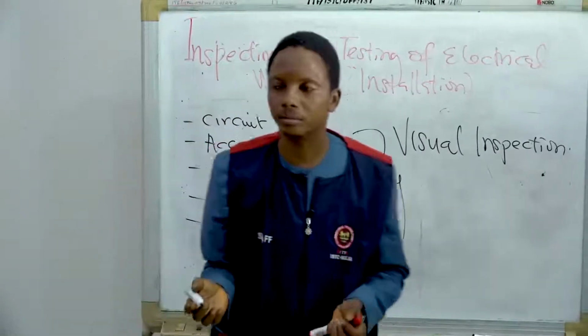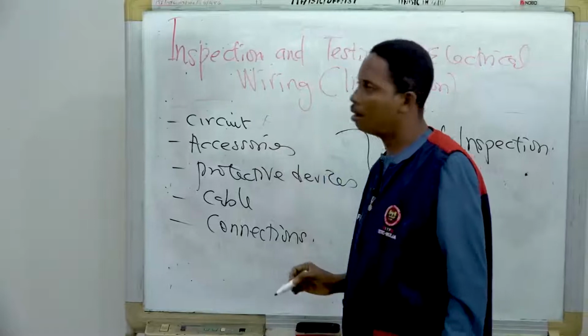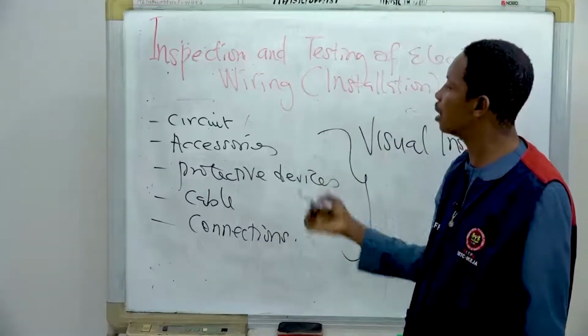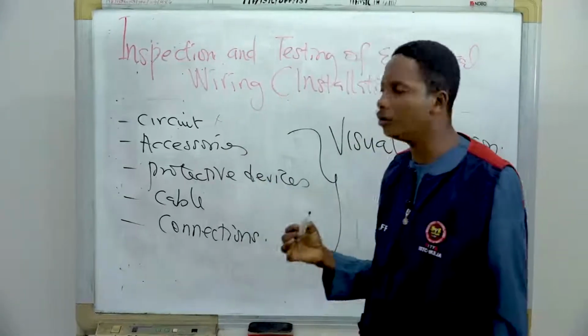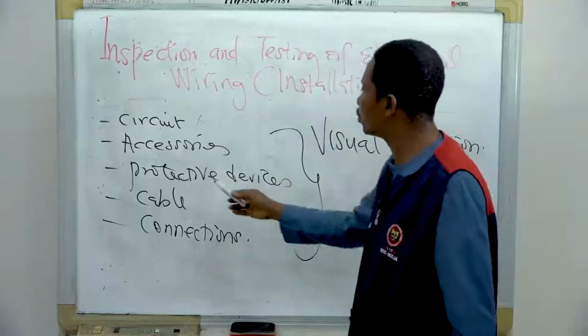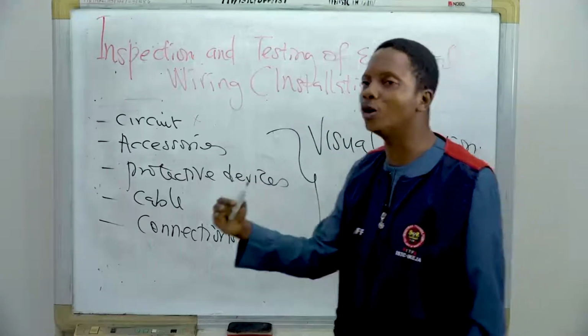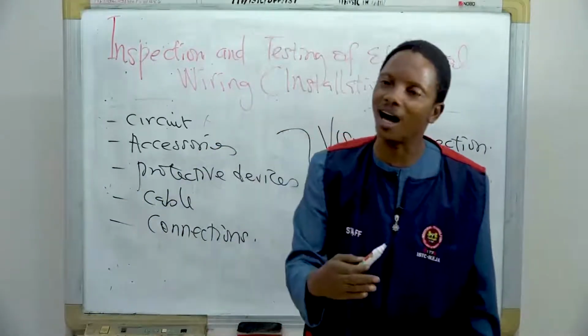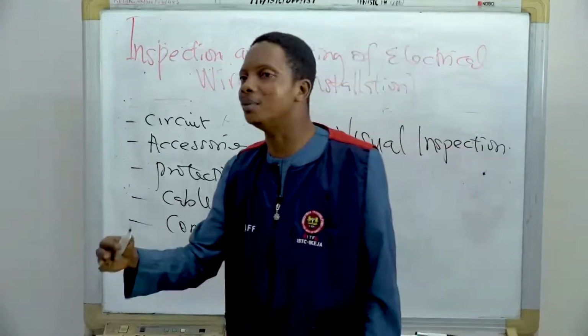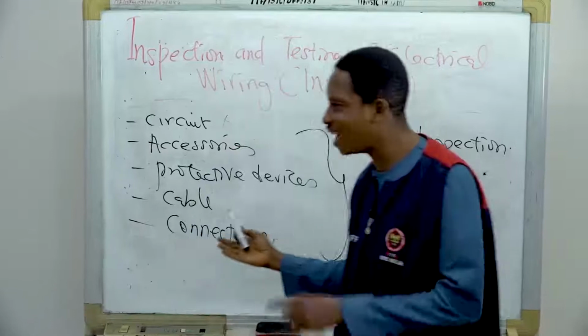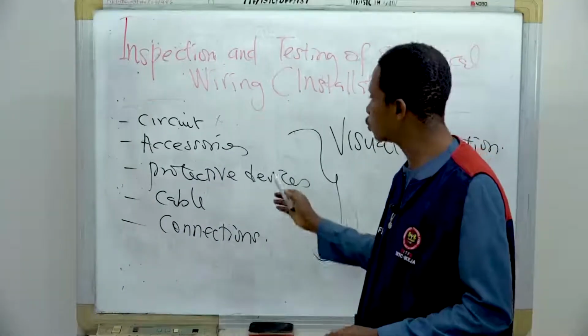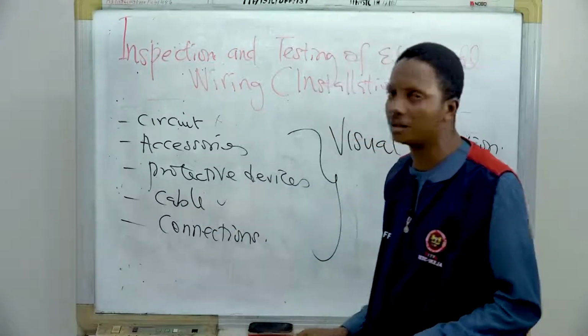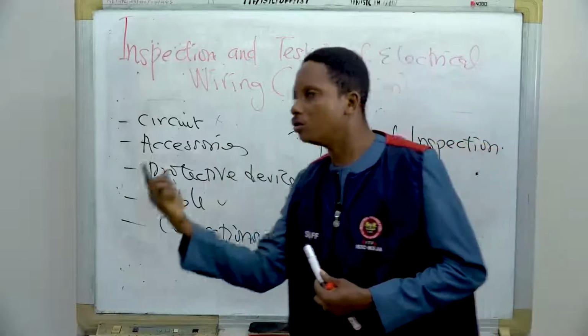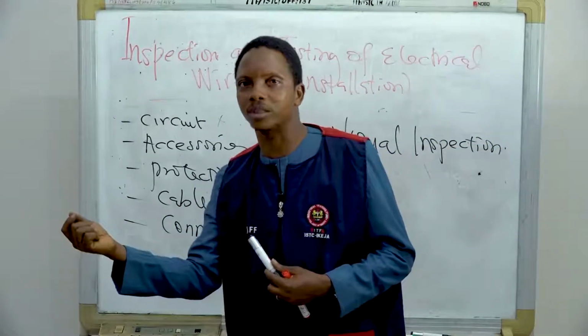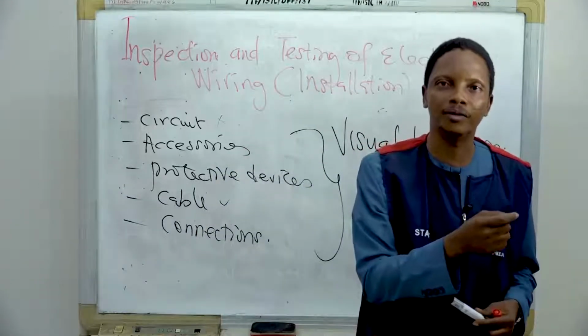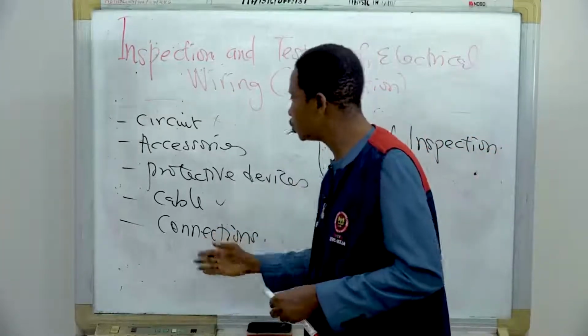Physical observation. You look at the circuits. Are they well done, especially from the sub-final circuits to the load? The accessory, are they original? Looking with your eyes. Protective device, do they conform to the load size, and are they original material? And you consider the manufacturer specification. Are all these things in line? Do they conform to IEE regulations? You look at the cable size. For instance, look at cooker units. The cable recommendation is 6 mm. Are they using 4 mm, 2.5, 1.5? Physical inspection. And then you check the connections.